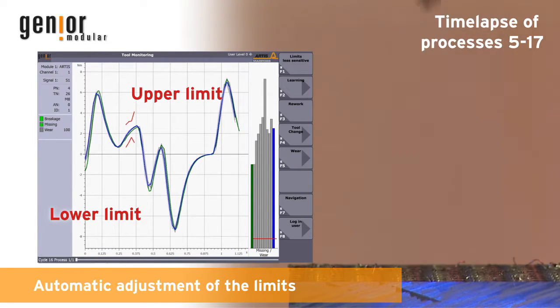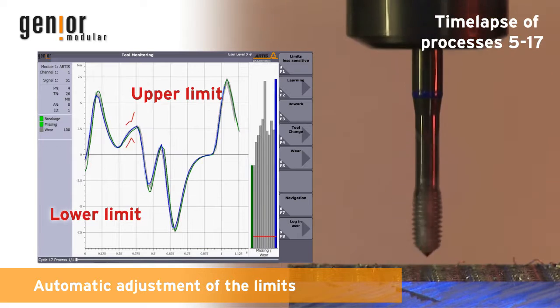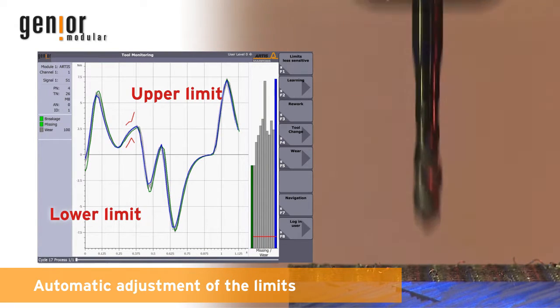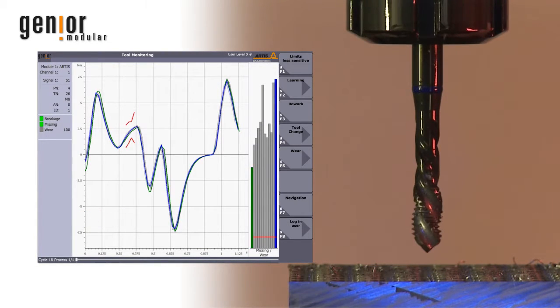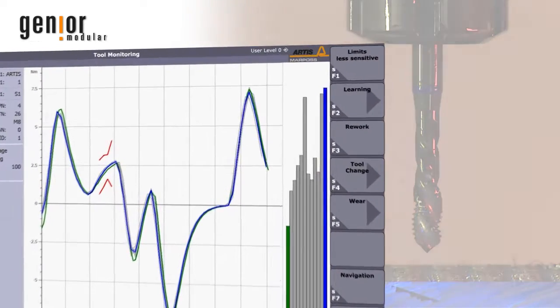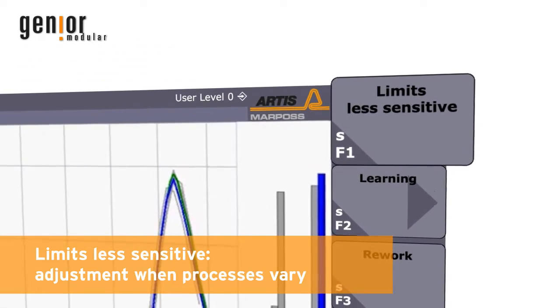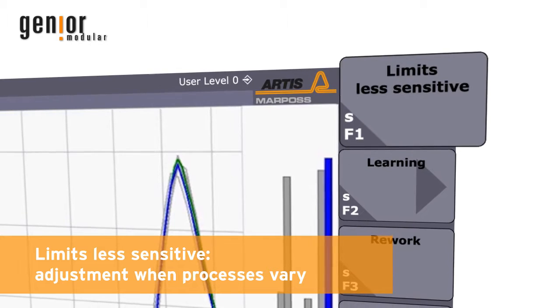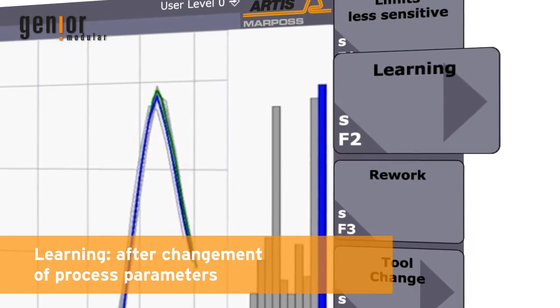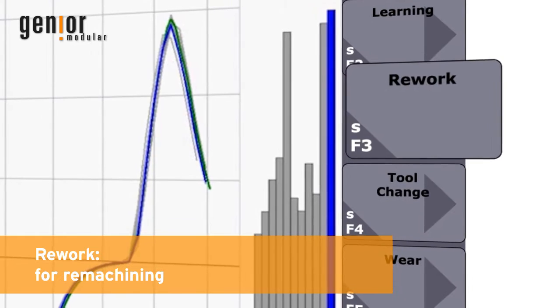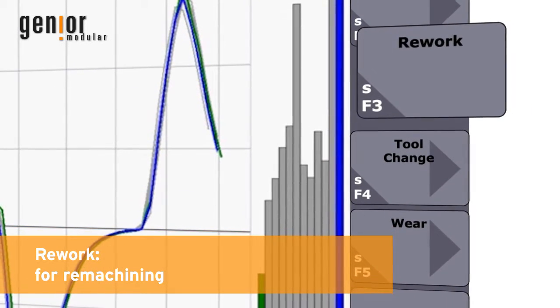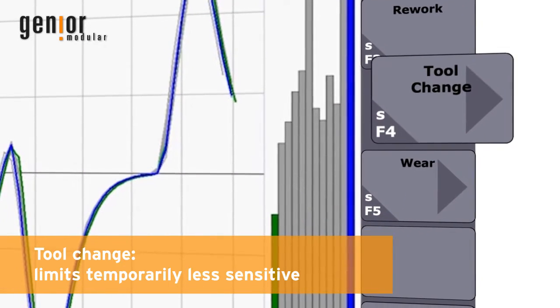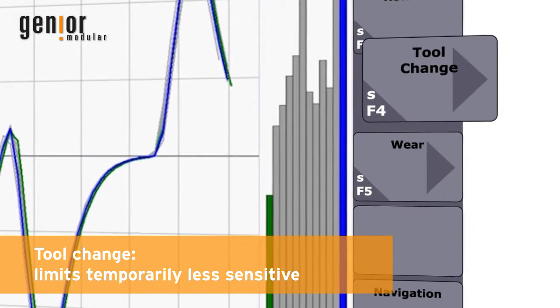The user has several options to reactivate the monitoring following an alarm. This is what the buttons on the right edge of the screen are for. One is used to compensate process deviations, another enables new learning cuts after a change of parameters, one deactivates the alarm limits for a single workpiece, and another sets the limits temporarily less sensitive.